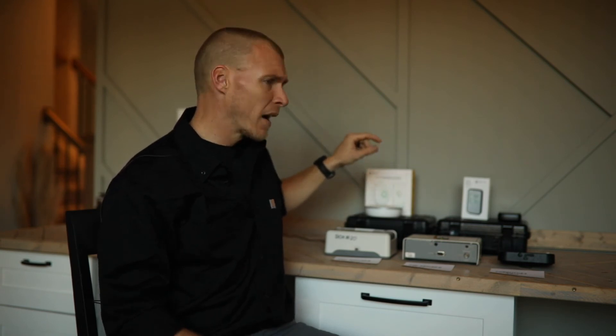So if you're a homeowner just looking to monitor radon, especially long-term, I love this device. You can hook up to it via Bluetooth. I've monitored my house with this device for six months and I love it — it shows me really good, accurate measurements. I compare it a lot of times when I've got a weekend where we're not using certain monitors, I'll bring them in and do some comparison testing just like I did this past weekend, and they're always dead on. These professional devices also have to be calibrated annually. That's part of having an approved device — once a year it gets shipped off to make sure the calibration is correct.